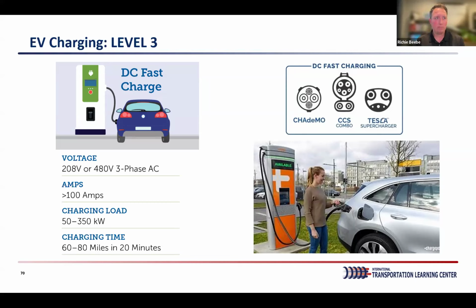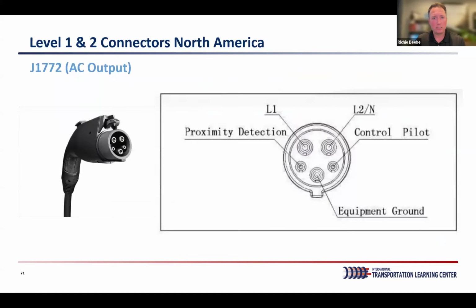Just to give a little more detail on the level 1 and level 2 AC connector, the J1772 - you have line 1 and line 2, your two smaller ports to the left and right are proximity detection and the control pilot, and then the equipment ground on the bottom. The one thing to point out is the equipment ground is the portion of that connector that makes the first connection point, and it's also the last connection point to be broken when you take the charging cable out of the vehicle. So you're always grounding it first, and that's the last to leave, to prevent any arcing, or if any arcing does occur, the equipment ground is there for protection.